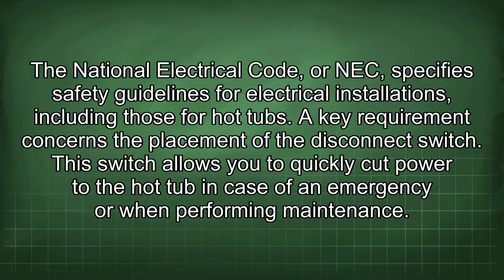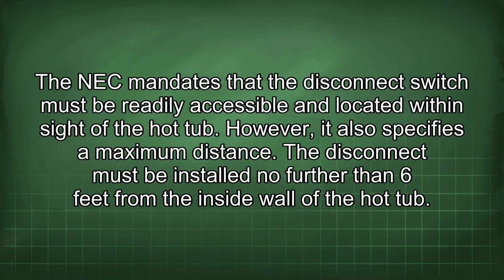The National Electrical Code, or NEC, specifies safety guidelines for electrical installations, including those for hot tubs. A key requirement concerns the placement of the disconnect switch. This switch allows you to quickly cut power to the hot tub in case of an emergency or when performing maintenance. The NEC mandates that the disconnect switch must be readily accessible and located within sight of the hot tub.